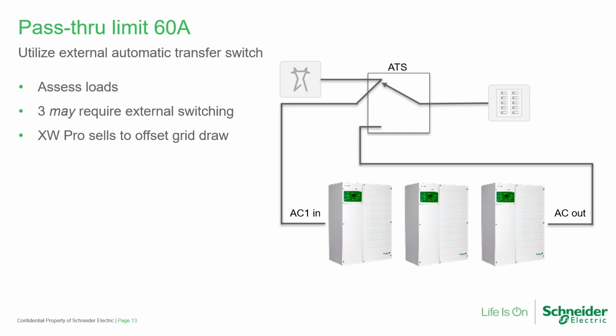If a motor surging at more than 100 amps happens to start at the same instant the transfer relay closes, then a welded relay may result. Consider a system that is shut down due to low battery and the customer starts a generator. If there are many motor loads, for example, refrigerators, freezers, air conditioners, well pumps, etc., then all these loads may be ready to start the instant the generator is transferred through by the XW system. This has happened and did result in a welded relay. Always consider the likelihood of such an event in your design and plan around it.